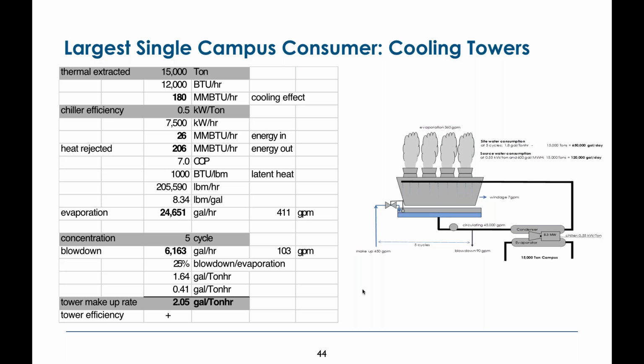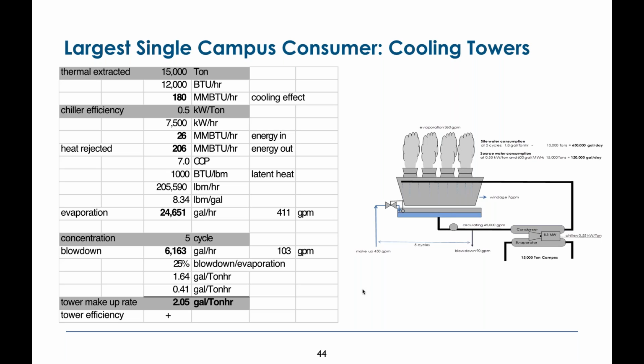or the energy in, if you convert that to BTUs, is 26. So the total amount of heat that you're pumping out of the cooling tower is a combination of the heat you're extracting from the campus plus the heat of compression, the energy that you're putting into the chiller to get the heat out. So that turns out to 206. Now, if you convert that total amount of BTUs we're dumping out the cooling tower into water, that turns into 24,000 gallons an hour to get 15,000 tons out.